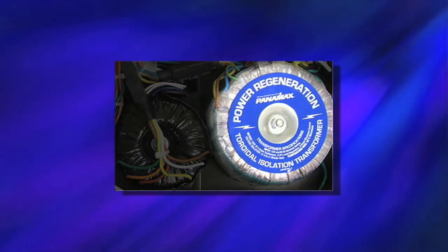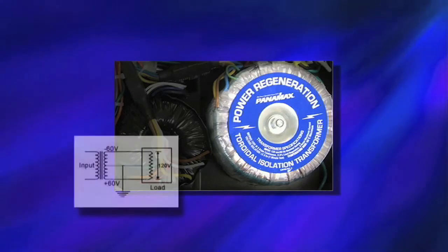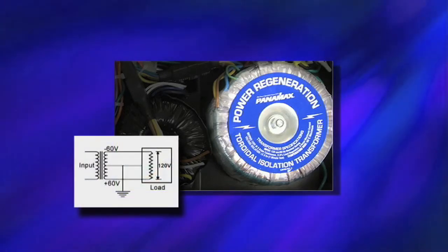A toroidal isolation transformer can regenerate power through magnetic coupling and allow the ground reference to be placed symmetrically between line and neutral. This is called balanced power. In this scenario, common mode voltages on the line and neutral are 180 degrees out of phase with each other and will cancel at the output.